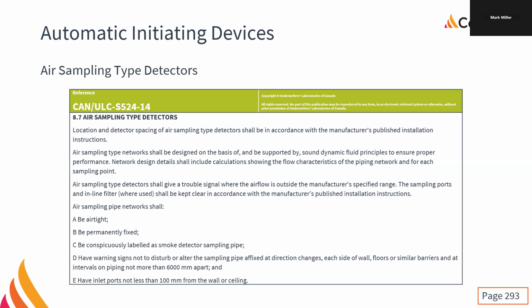they're stickers, every time we change direction. So at each elbow, on each side of a wall or floor, anytime we go through anything, we have to put the warnings on. And other than that, every 6 meters, we have to put warnings on. We have to put warnings on everywhere to keep people from messing with it because that entirety of that tubing network is part of that device. It's part of the fire alarm system, right? And people can be slow to recognize that.